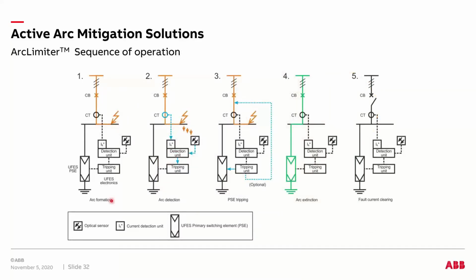So here is another sequence of events, right? When you have an arcing fault on your switchgear, you have a CT that looks for the current and the light by the arc flash relay, and in conjunction of these two, it's going to send a tripping signal to the tripping unit that in turn puts a bolted fault on your system. And as a standard, we can also send a trip signal to your upstream breaker.